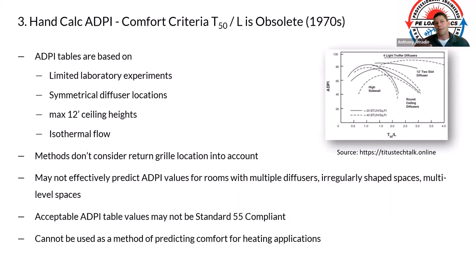Look at what we have today. Some of you may be familiar with the hand-calc method of the Air Diffusion Performance Index, or ADPI, where we look at the isothermal throw at 50 feet per minute and the size of the room, the characteristic length. This is how I've placed diffusers and sized them. I haven't done this on every job, but on most jobs it takes time, looking at these tables. By the way, these tables are from the 1970s—honestly, they're obsolete, and have nothing to do with the person or where they're located. It's based on laboratory experiments with 9 to 10 foot ceiling heights, although they claim it's good for up to 12 foot ceilings.